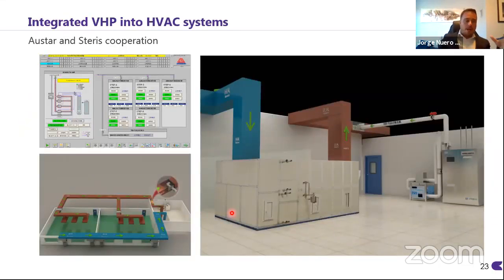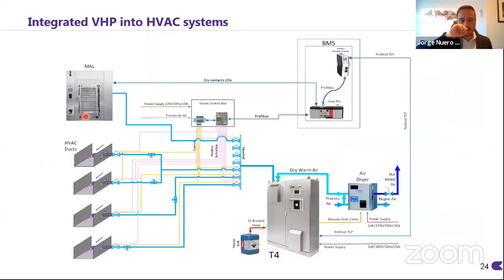So we are going to see how to make the decontamination of the HVAC system. As far as I know, AUSTAR and Steris have had a long cooperation, and the Steris system is the only system, as far as I know, maybe there are new systems now, that allows you to make the decontamination not only of every single room inside a biosafety level 3, for example, but also of the complete ducting system, including the HEPA filters installed in it. So this is how the control system looks like. You will see here in the next slide. This is very schematic, just with Steris. This is a T4, the big generator. We can deliver VHP to every single room, but not directly to the room, but through the HVAC ductings. Or we can also deliver to a VHP pass box, as in the sample here before.